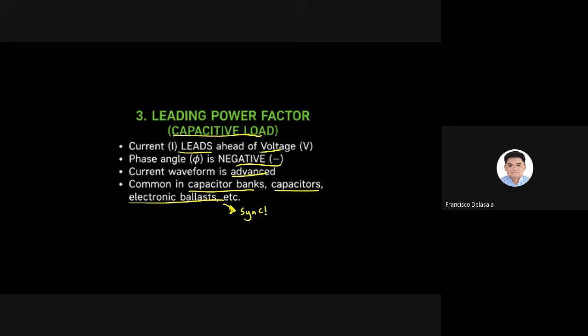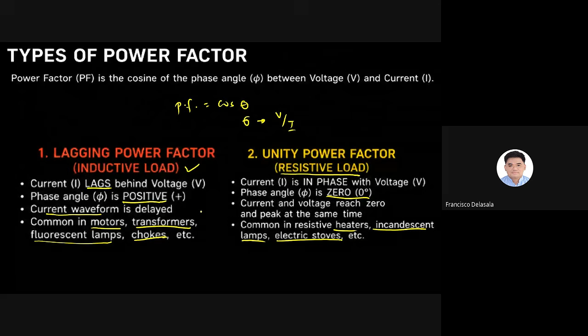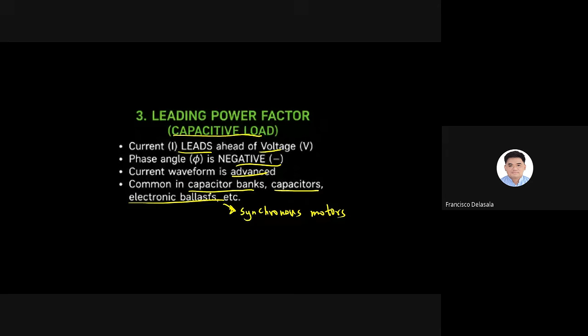There's another one usually asked in the board exam: synchronous motors. What we want to avoid in our electrical system is having a very low lagging power factor, meaning it's too low. To correct that, we try to introduce a leading power factor by adding capacitor banks, capacitors, or synchronous motors to raise our power factor. Okay, so we have here the power factor triangle.